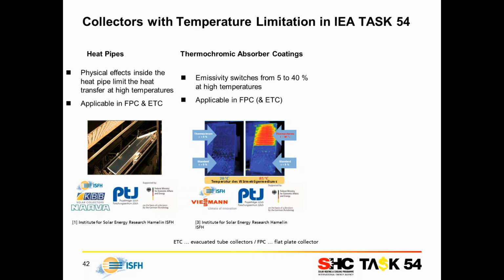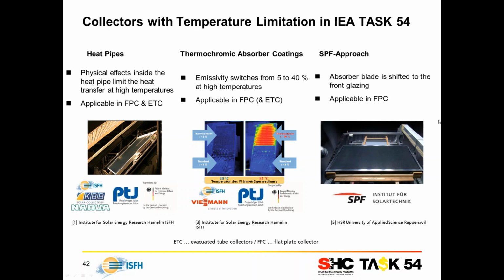Another approach is given by the SPF, the Institut für Solartechnik, at the University of Applied Sciences in Rapperswil. The approach is based on shifting the absorber to the front glazing. That means the distance between the absorber and the glass is minimized at a high temperature level. Also the heat losses are increased for that, and the stagnation temperature is reduced.